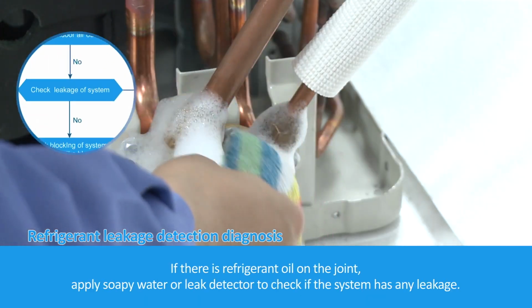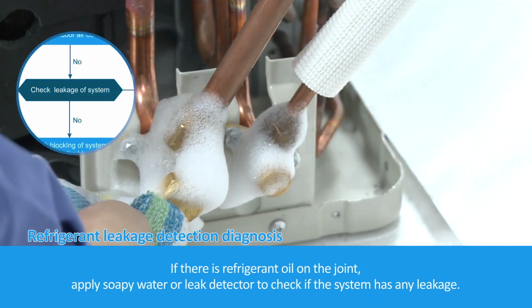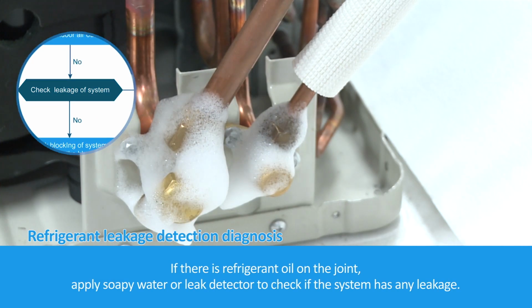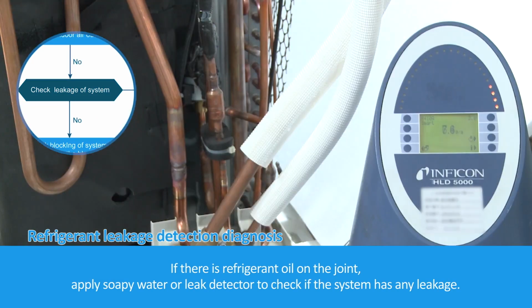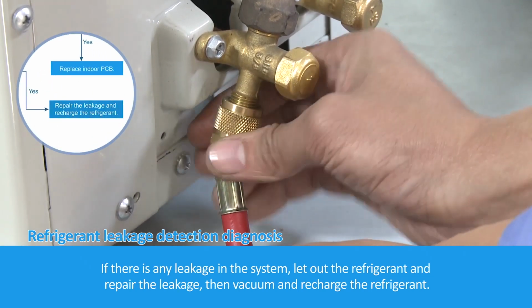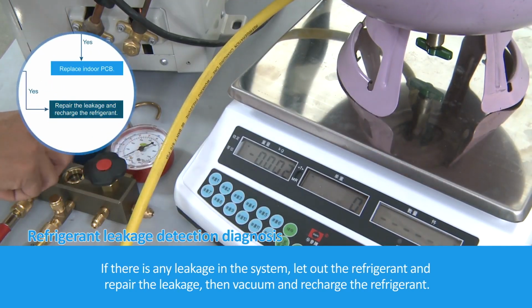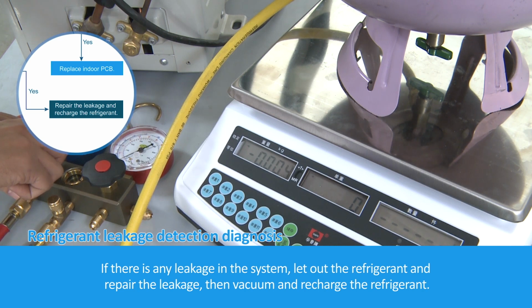If there is refrigerant oil on the joint, apply soapy water or leak detector to check if the system has any leakage. If there is any leakage in the system, let out the refrigerant and repair the leakage, then vacuum and recharge the refrigerant.